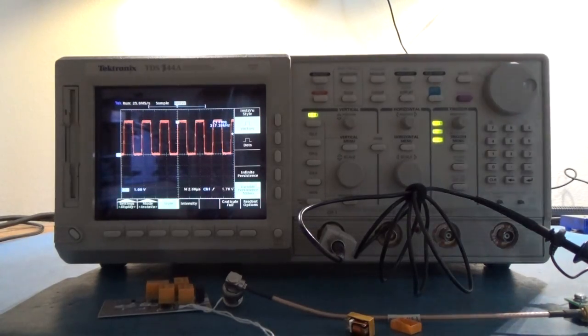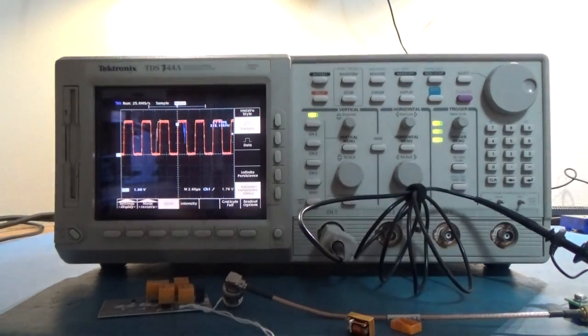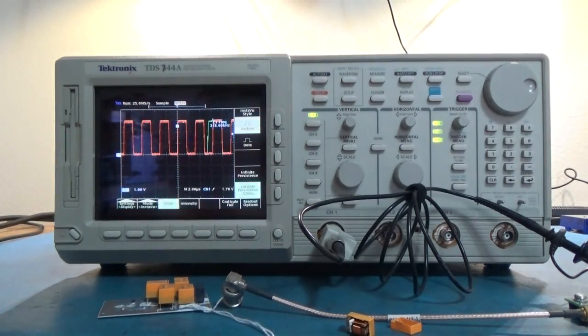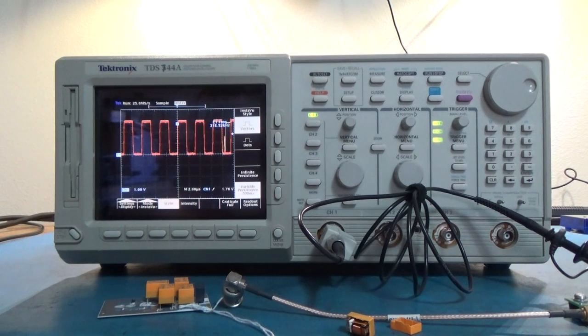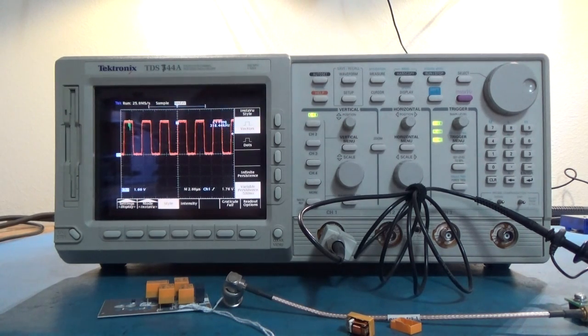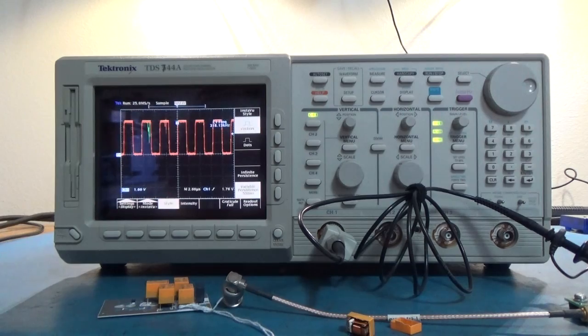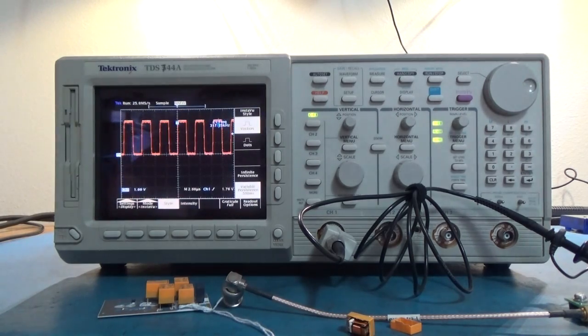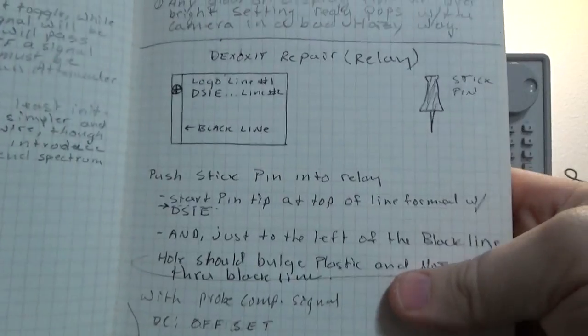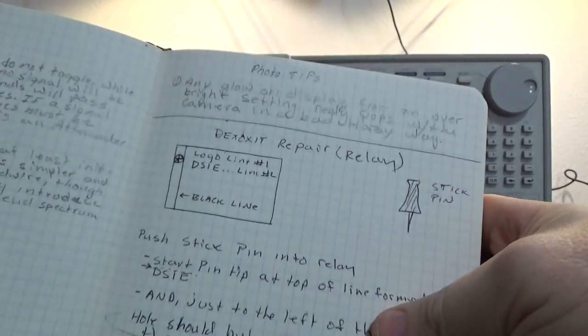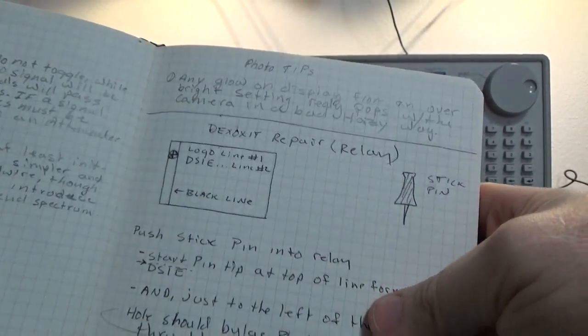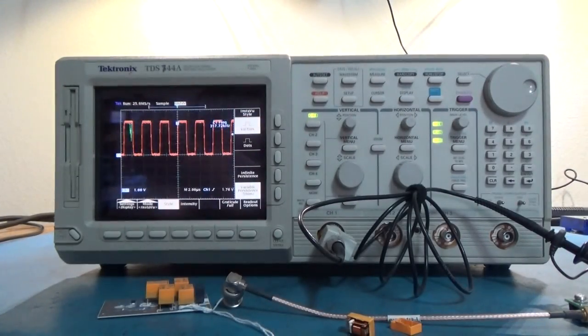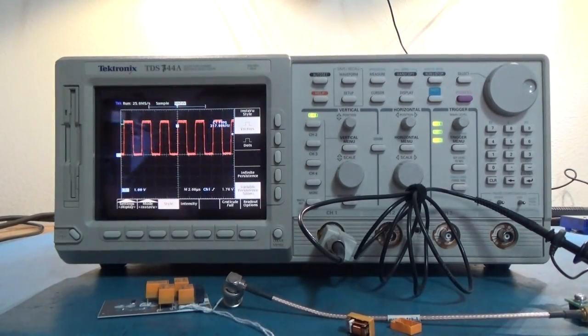Especially when you're calibrating, a lot of times you can see that it's failing at 500 MHz at the 10 mV setting or something. If it works, let me know and we'll tell the world and everybody will be able to fix that problem. But the relays are the main problem on these scopes. Sometimes the power supplies die.